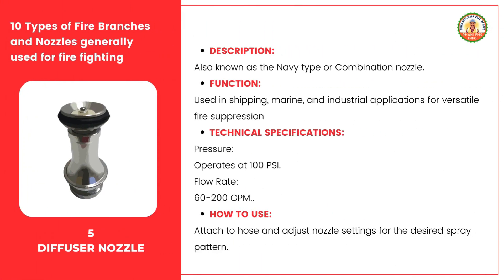The diffuser nozzle, also known as the Navy Type or Combination Nozzle, is widely used in shipping, marine, and industrial applications due to its versatility in fire suppression. It operates at a pressure of 100 psi, with a flow rate ranging from 60 to 200 gallons per minute, allowing for flexible water flow to handle different firefighting scenarios. To use it, securely attach it to the hose, then adjust the nozzle settings to select the desired spray pattern, providing the right water distribution for different types of fires.